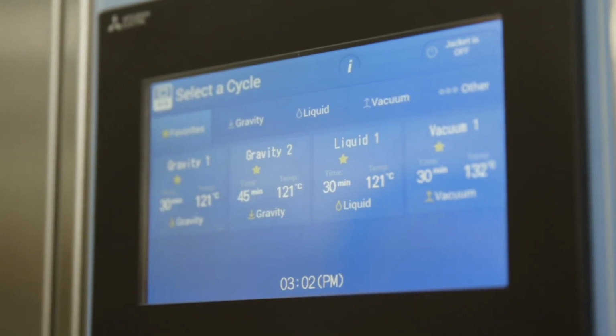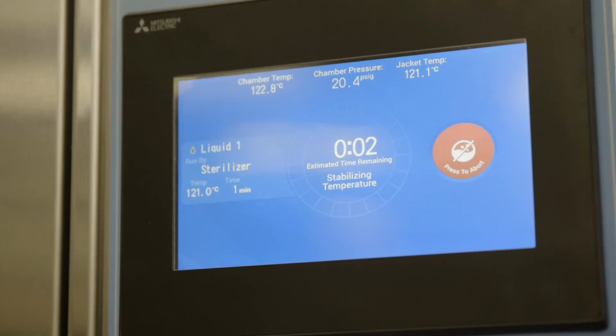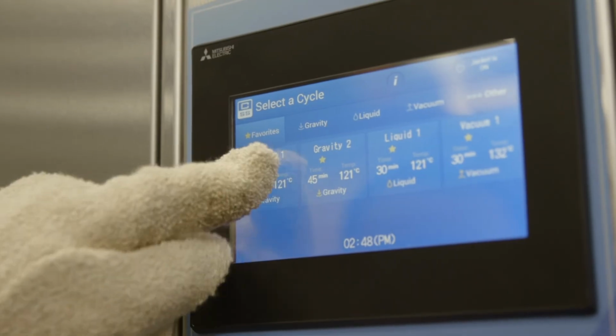Choose the appropriate cycle for the goods inside the chamber. If you are unsure which cycle to select, consult the autoclave manual for instruction on how to choose the correct cycle parameters. Note that sterilization time and cycle type will vary depending on a number of factors, including the size of the load and the type of load. In our case here today, we're sterilizing red bag waste, so we'll select a gravity cycle.